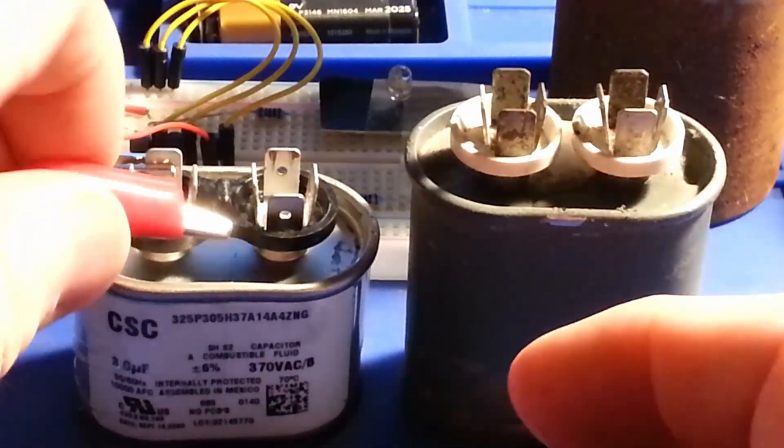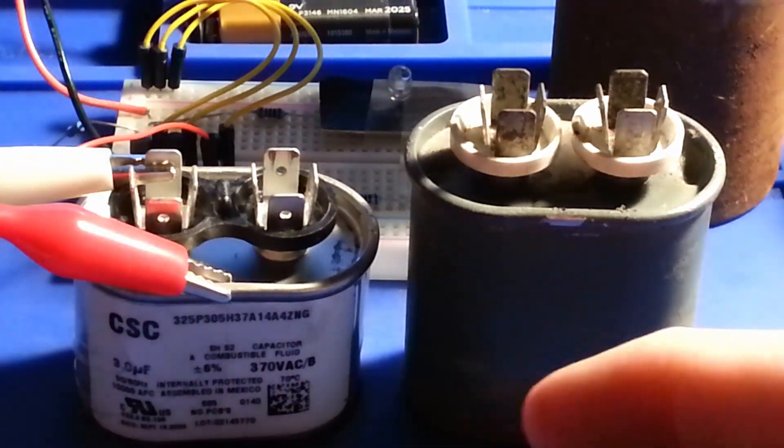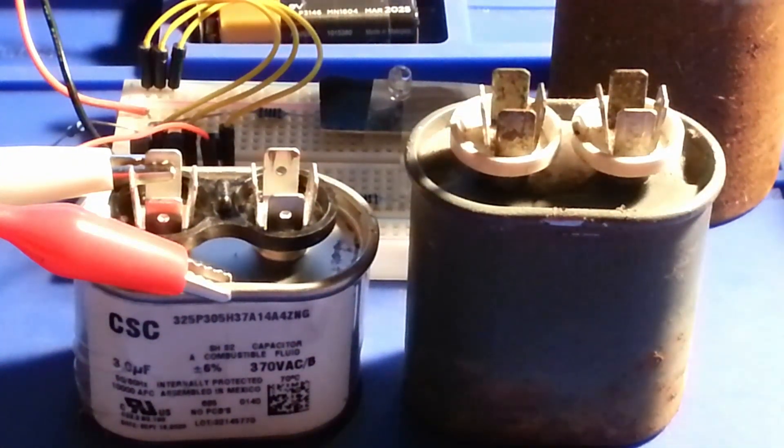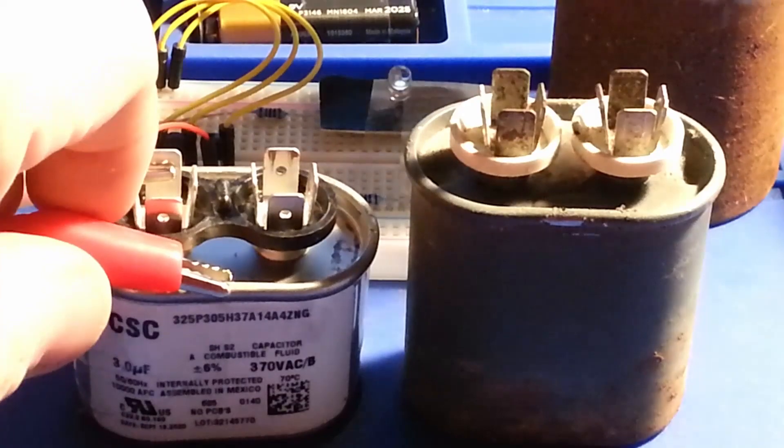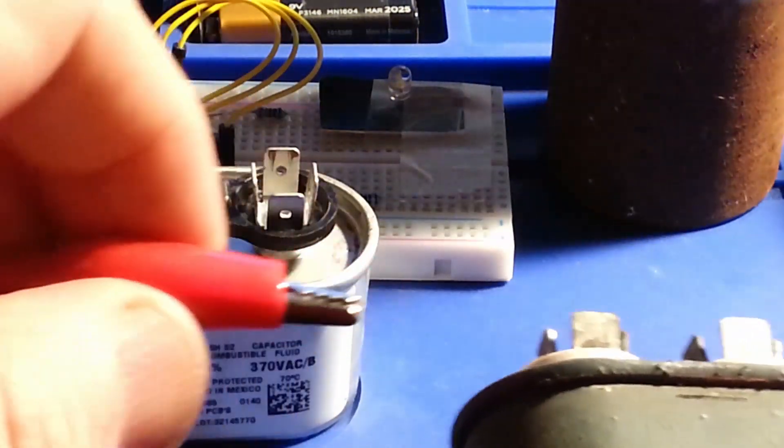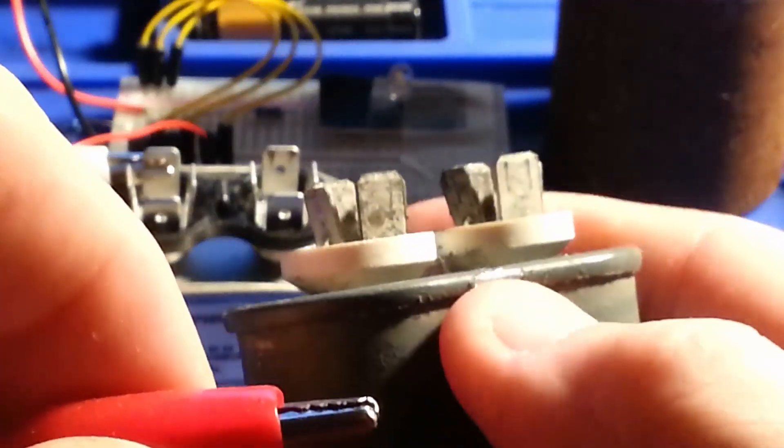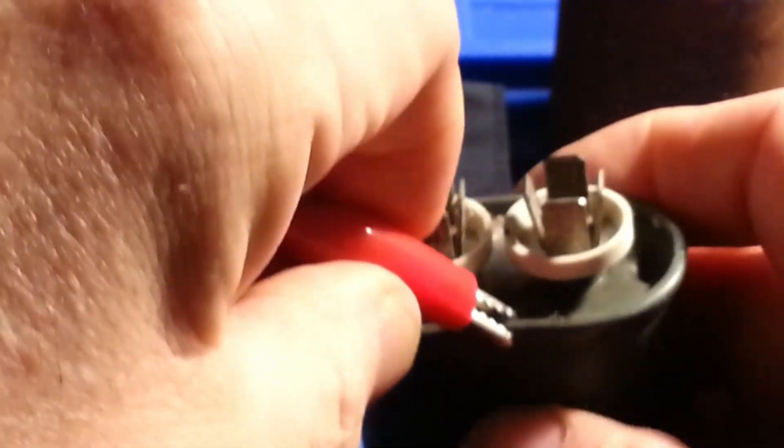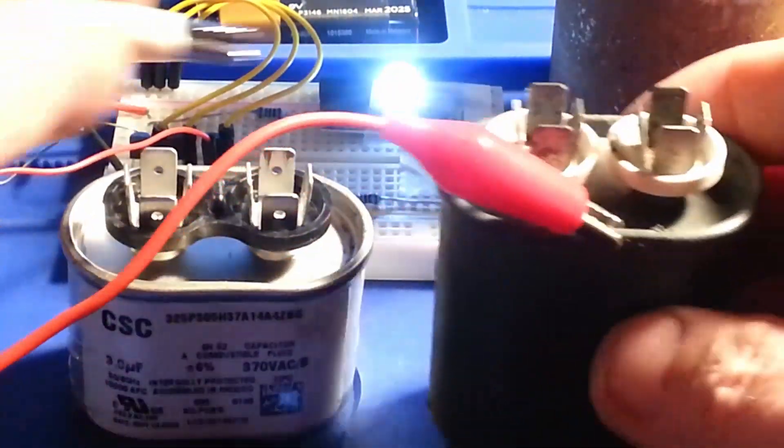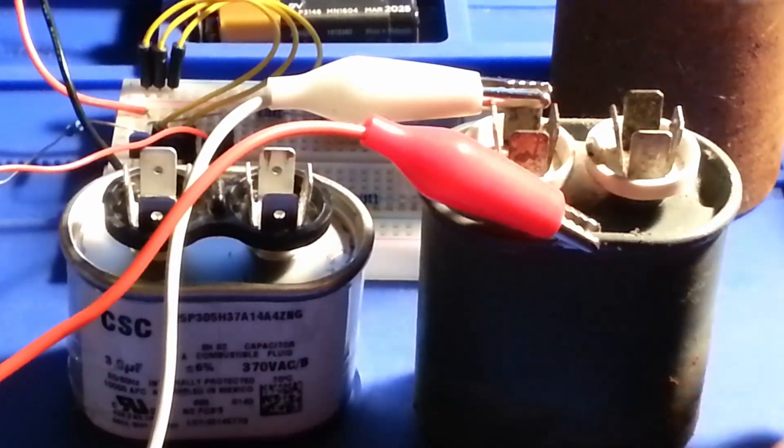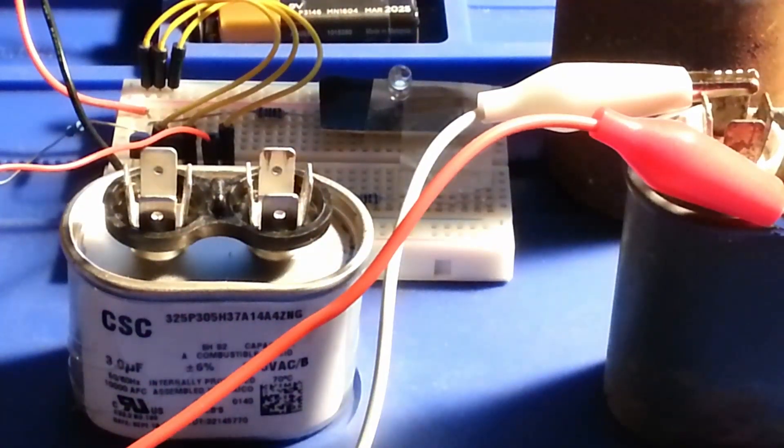Going into the connection on the case though, there is very little to no resistive fault indicated on the old one or the new one. I mean on the old one I've got some paint scraped off over here to get a good connection right there. And if you can see, the LED is just lighting up just a little bit more, but as far as the qualitative measurement, there is no direct continuity between the case and the internal capacitors on that old one.